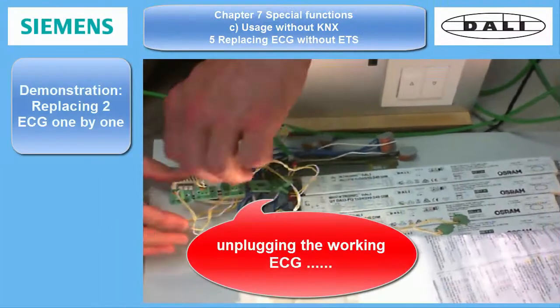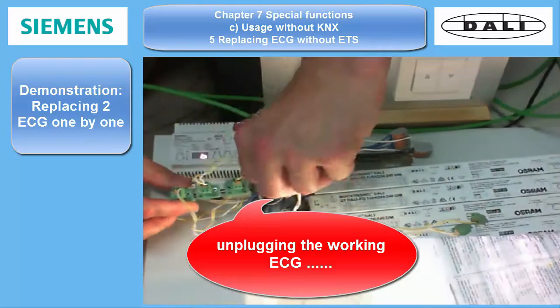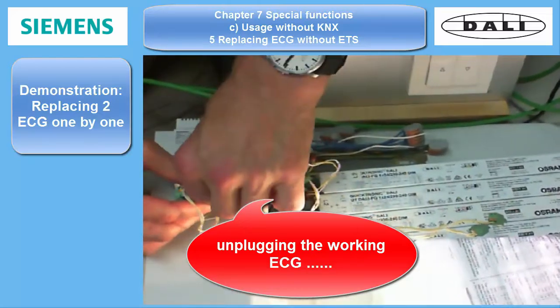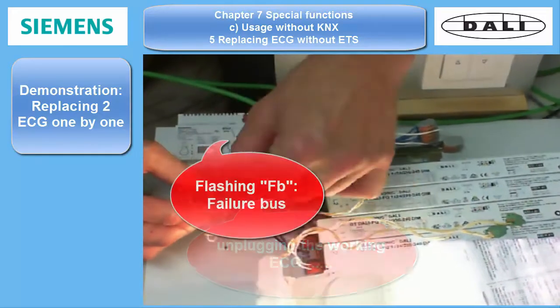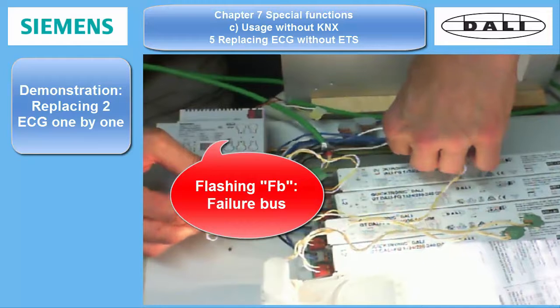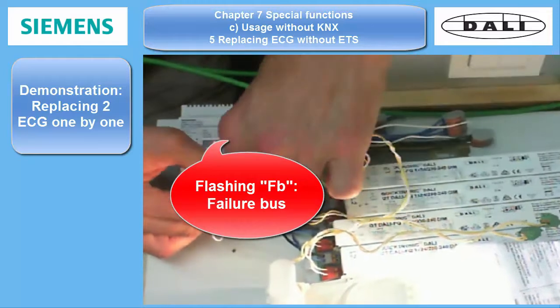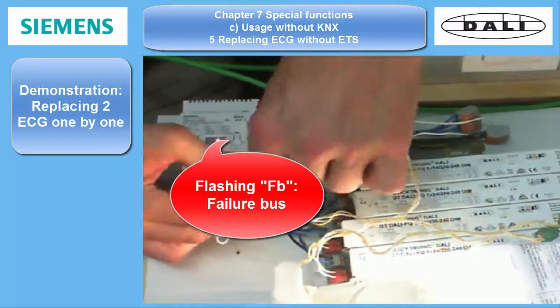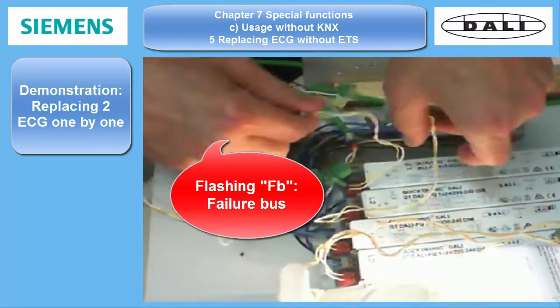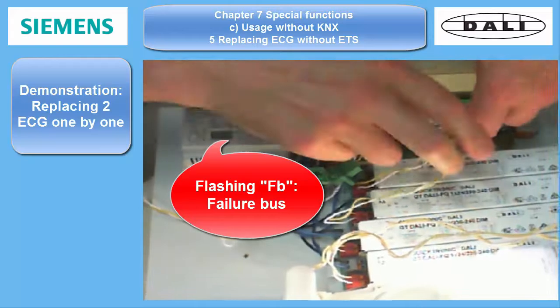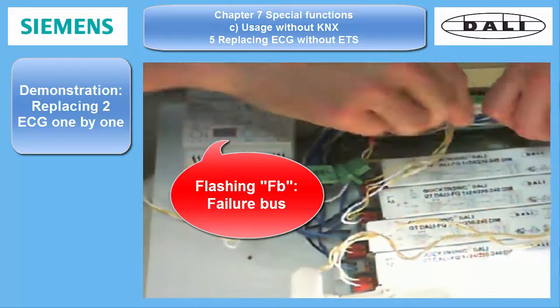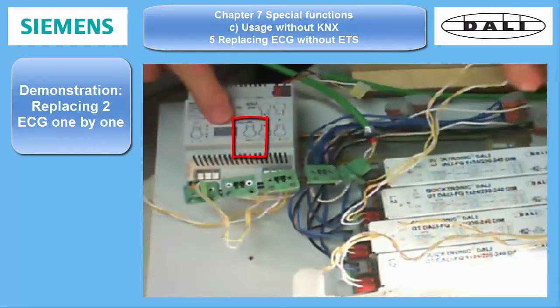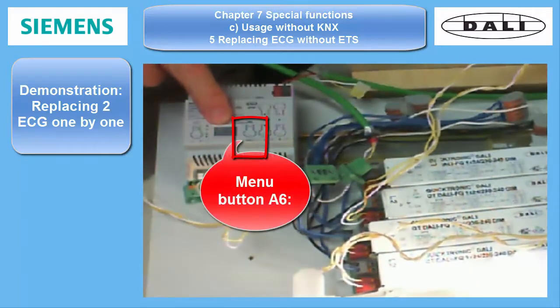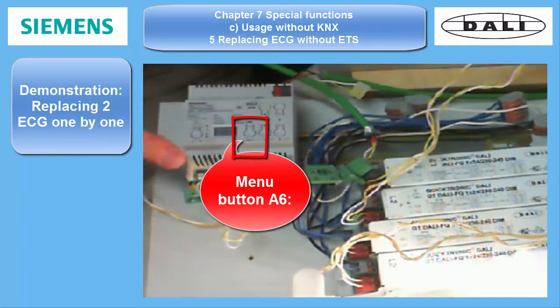Now I simulate the dropout of both ECG by unplugging them from the DALI bus. Watch the front side display of the DALI gateway. From B, bus active, it turns to FB, failure bus, signalizing that something is wrong. To find out what is wrong, press the menu button A6 according to the BMA once.